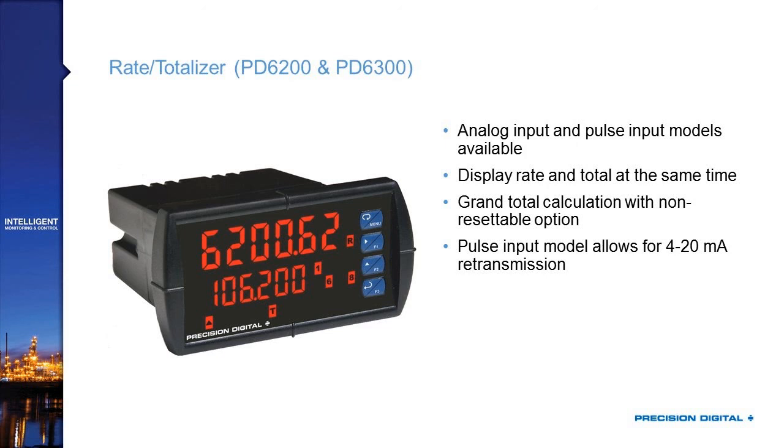For those of you who work with flow, the PD-6200 and PD-6300 are your basic flow meters, available with analog 4-20mA inputs from flow meter preamps or direct pulse inputs. Because of the two-line display, you can show flow rate and total simultaneously. It also has grand total calculations, a non-resettable total option for regulatory environments, and because it shares ProVu outputs, you can use it to convert a pulse input from a flow meter into a 4-20mA output to run back to your control room.